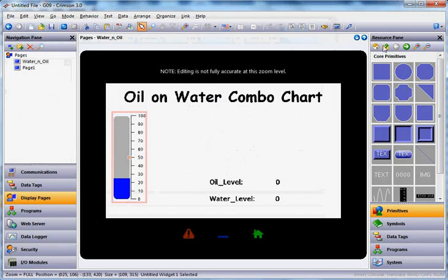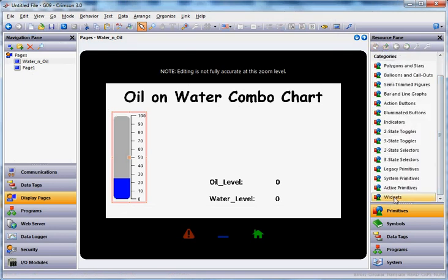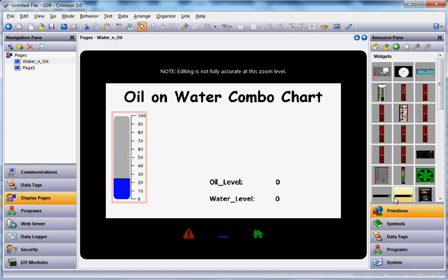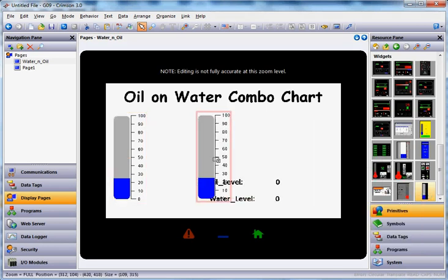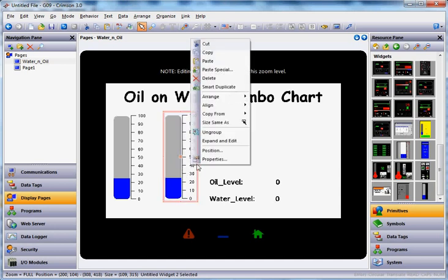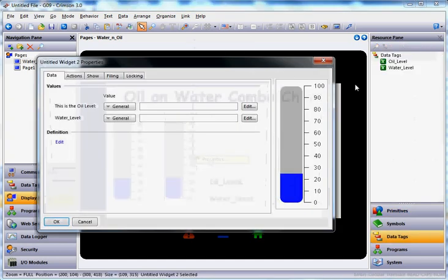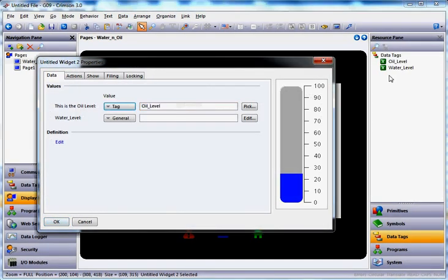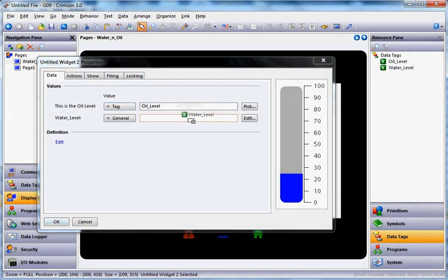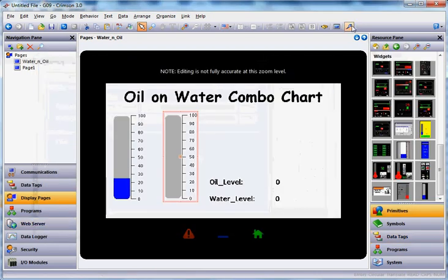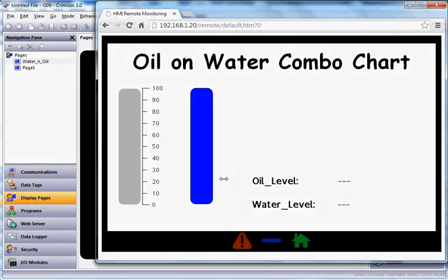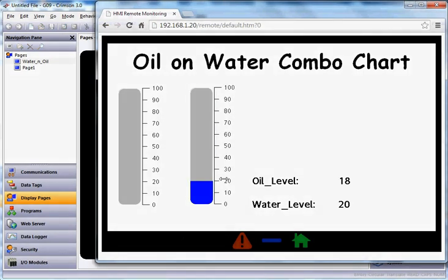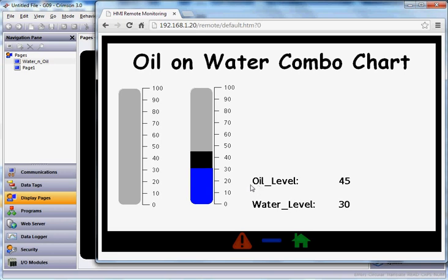And now if I go over here to the right side and click on the home directory of my primitives, come down here and click on the widgets directory. And in the widgets directory, I think way down here in the bottom, should be my oil chart since I've got a bunch of widgets already in here. And I simply would just grab this guy out and drag it on the screen like this. And if I want to link this to my tags, I simply go right click and go to properties. And I just merely need to grab the oil level, drag it right there, and the water level and drag it right there. Hit OK. And go ahead and download this to my screen. And let's see how it works. And there you can see as I move my oil level up and down. This one is not working anymore because we widgetized it and it broke the links to the thing, to the real IO. But this one, we widgetized, we linked it. So you can see it works perfectly well and you can reuse that graphic over and over which is pretty cool.